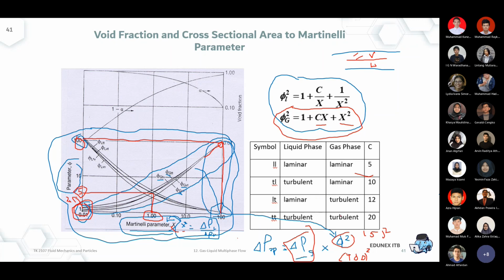Of course, the worst pressure drop will happen when we're working in a turbulent regime, because of the high velocity, and because the direction is not in a clear order. So for the correction factor C, if you have a combination of turbulent liquid and turbulent gas, the correction factor becomes the highest one, 20.